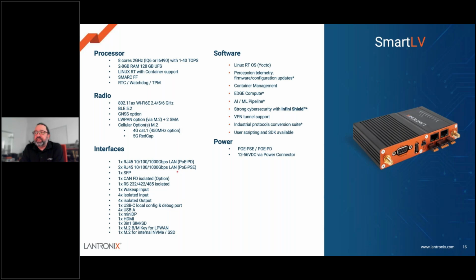We have CAN-FD inside for some use cases like power storage. CAN bus is normally the standard protocol to control and read out data from storage. Then the traditional ones to read out Modbus and standard power meters: we have RS-232, 422 and 485 for Modbus, isolated, and you can program which variant you want.